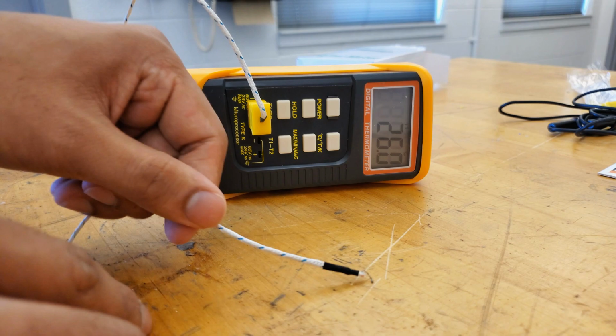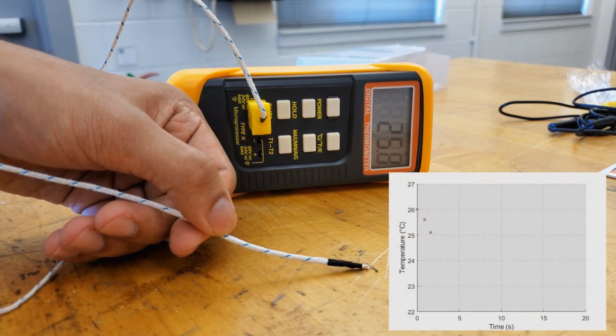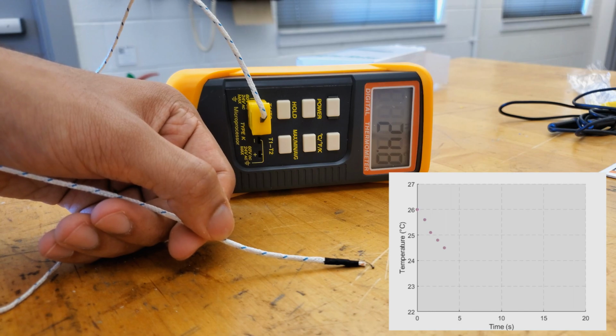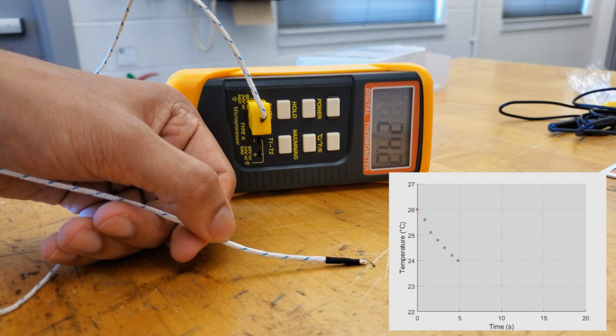To do so, hold the thermocouple by the white insulated wire to the surface. Taking an accurate measurement is dependent on effective heat conduction from the surface to the metal probe. You'll notice that the temperature will either be increasing or decreasing at this point, as soon as you touch the surface, depending on whether you just measured a hotter or colder surface.